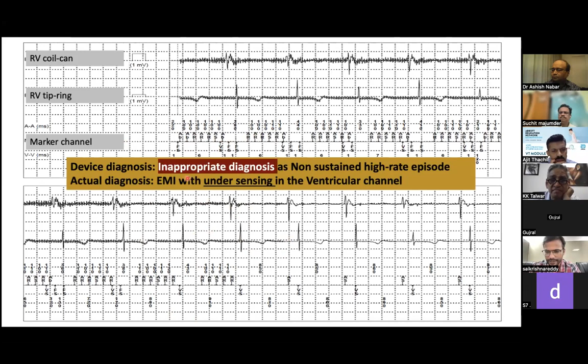The top one there is the atrial channel, not the RV coil to can. Oh, sorry. Yes, sir. It's the atrial channel, not RV coil to can. So the first one is atrial, the second one is near field, and then this is the marker channel. So basically the device is able to detect the signals only in the atrial channel, not in the ventricular channel. Which is why the device is not able to label this event as noise, but rather, because there are very high rate episodes which were non-sustained, it labeled them as non-sustained high rate episodes. These are all intermittent. So the device diagnosis was inappropriate, non-sustained high rate episodes, but the actual diagnosis is EMI with undersensing in the ventricular channel.